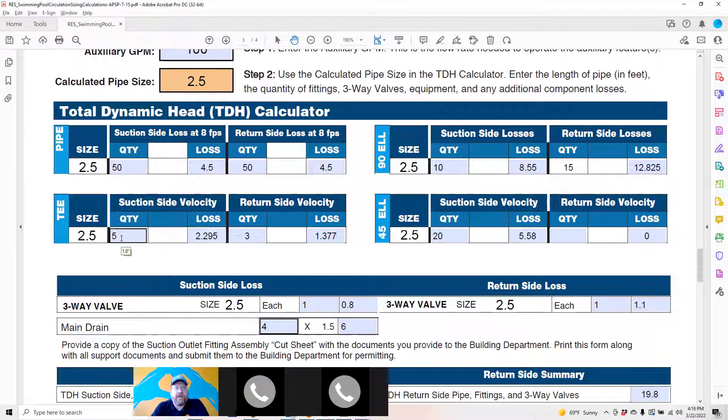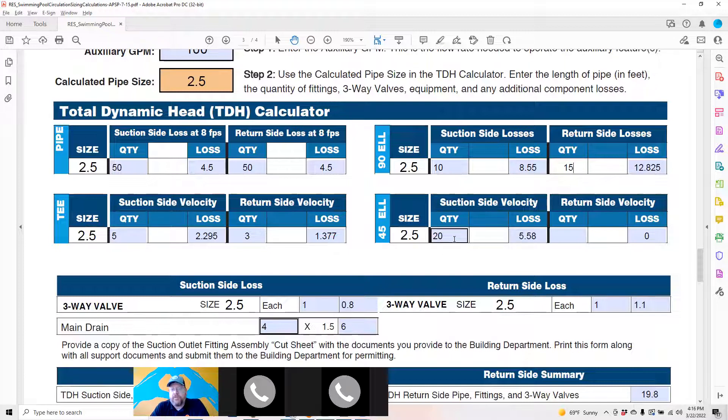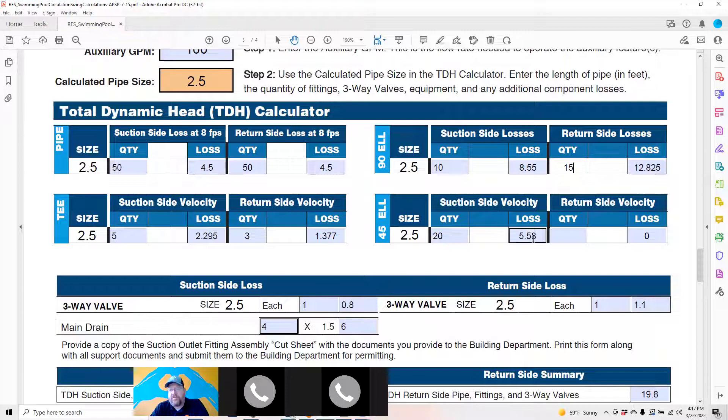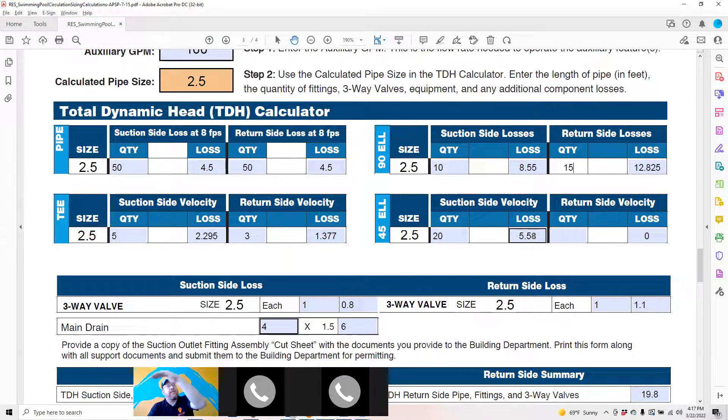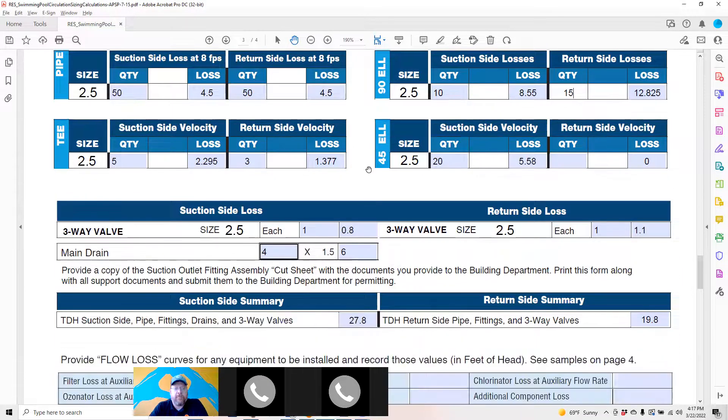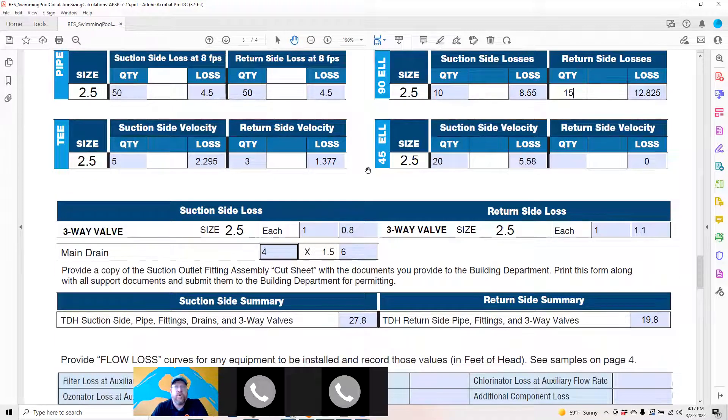Any tees used to split off for your returns or for the manifold will be calculated here on the suction and return side. If you are opting to use 45s instead of 90s, there's a much more efficient way to flow water. As you can see, 20 45s accomplish the same turn as 10 elbows with 3 feet of head lower—less friction. So gradual sweep instead of the hard elbows, a lot more efficient and will help you build a better, more efficient, quieter pool.